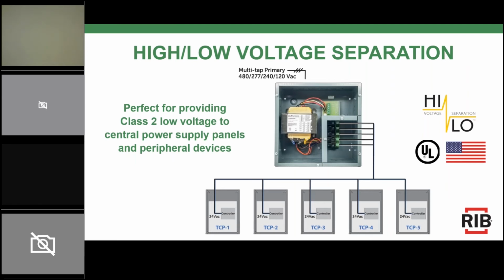Speaking of the low voltage compartment, I wanted to dive into that a little more. Going back to the origins of the product, it goes back to 2012. There was a job site for a national laboratory in Chicago that required all engineers and technicians to equip full arc flash protection suits to access any panel with exposed terminals of more than 50 volts. This requirement caused workers to lose countless hours of productivity equipping protective suits, face shields, and rubber-soled shoes just to access the panel.